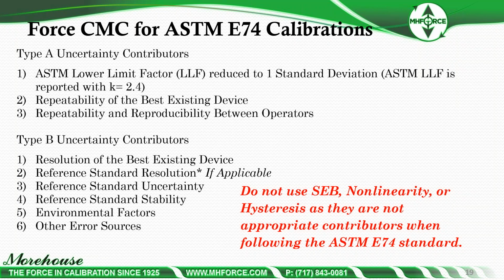Anyone familiar with the ASTM standard knows that the lower limit factor is reported with K equals 2.4. We have repeatability of the best existing device, and then we have repeatability and reproducibility between operators, which we will discuss. What to take? Do you take both? Do we just take the reproducibility? A2LA R205 asks for reproducibility. The other ABs are asking for reproducibility.